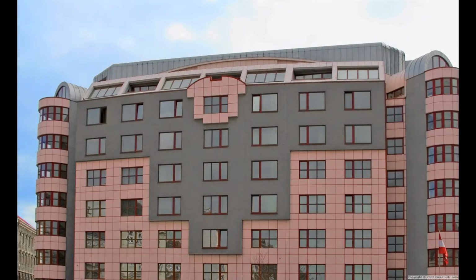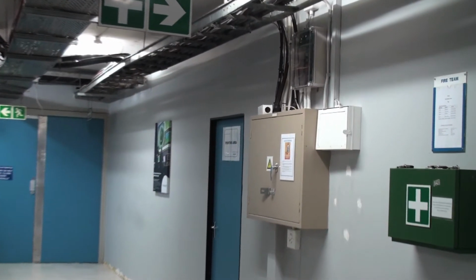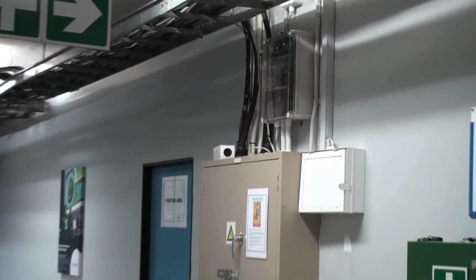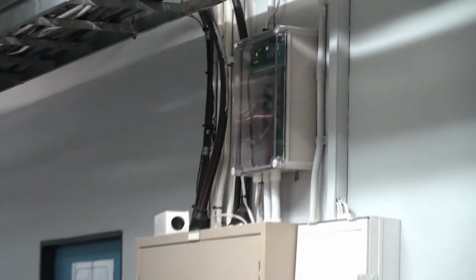The project at the headquarters of a major defense contractor was a typical large installation. We established a network of 14 16-channel PowerGuard units, which controlled 250 air conditioners. It's important to note that PowerGuard's very complex algorithms ensure that no air conditioner will ever be turned off for more than 9 minutes. The switching cycles are also not less than 1.5 hours apart, ensuring that comfort levels are not compromised. Chances are good that nobody will be aware of this intervention.